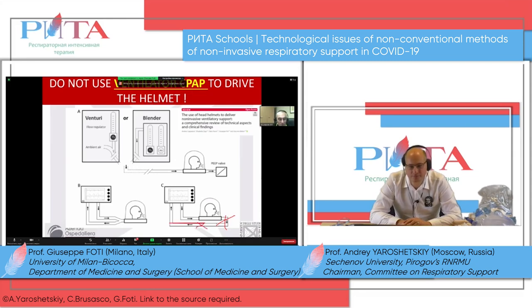No, flow must not go back on the ventilator. The ventilator should only provide flow in this one direction, one limb, and the modality should be...